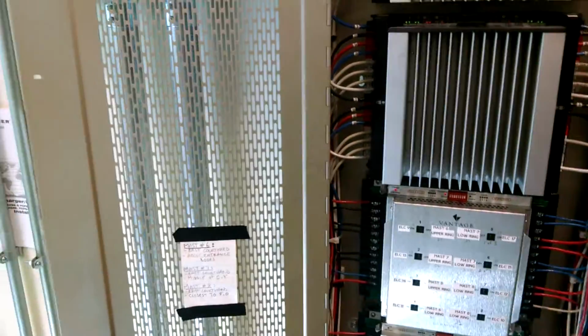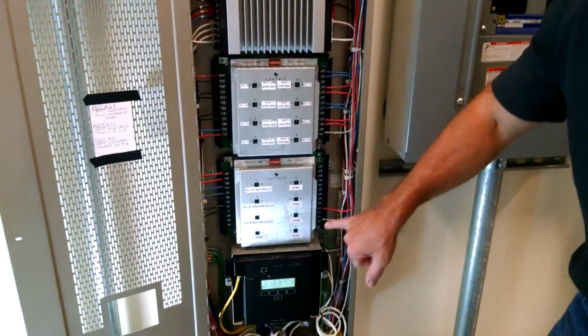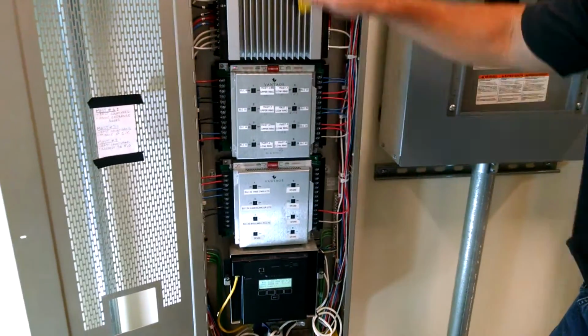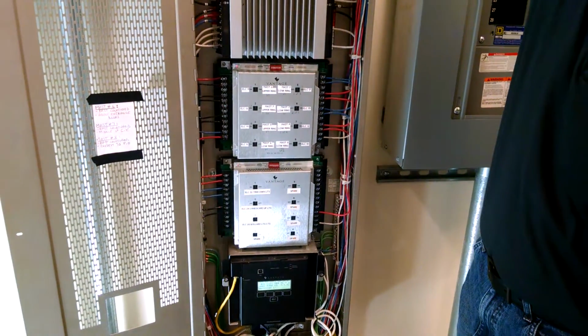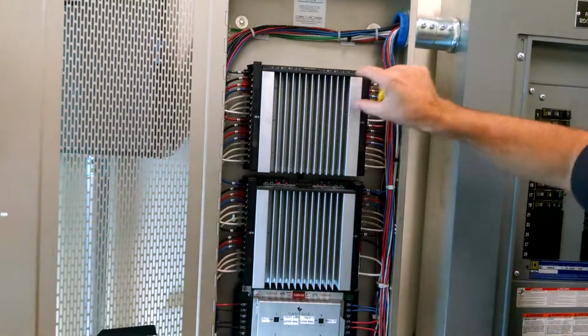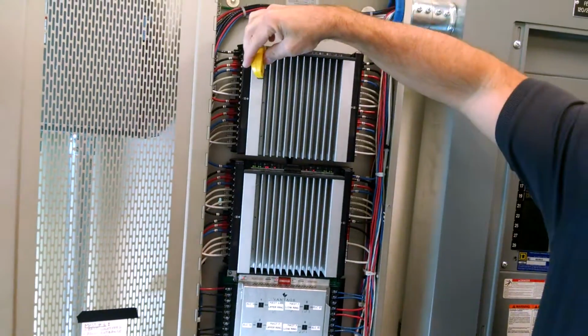And you use the same yellow bypass? Correct. Actually, I've done that. On this one, it uses a different one. It does not use this. This is just the two dimmers. Just does dimmers. Will that only bypass one circuit at a time? One circuit. So you've got 3 switch legs. Yeah, 3 switch legs, 3 switch legs, 3 switch legs. This is 1/4. This would be 3, 3, 3, 3. Gotcha. So you've got 4 devices in there.